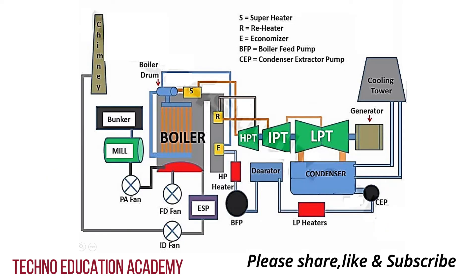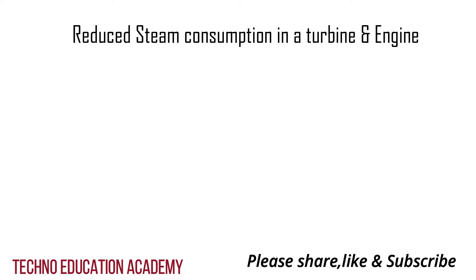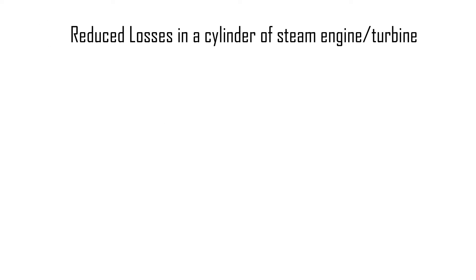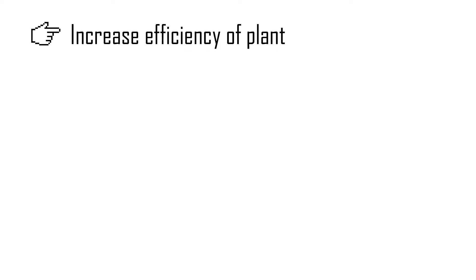Small boilers are not provided with a superheater. The following are the advantages of superheated steam: first, steam consumption of a turbine or engine is reduced; second, losses due to condensation in the cylinder of a steam engine and the steam pipes are reduced; third, erosion of the turbine blades is also eliminated; and fourth, the efficiency of the steam plant is increased by using superheated steam.